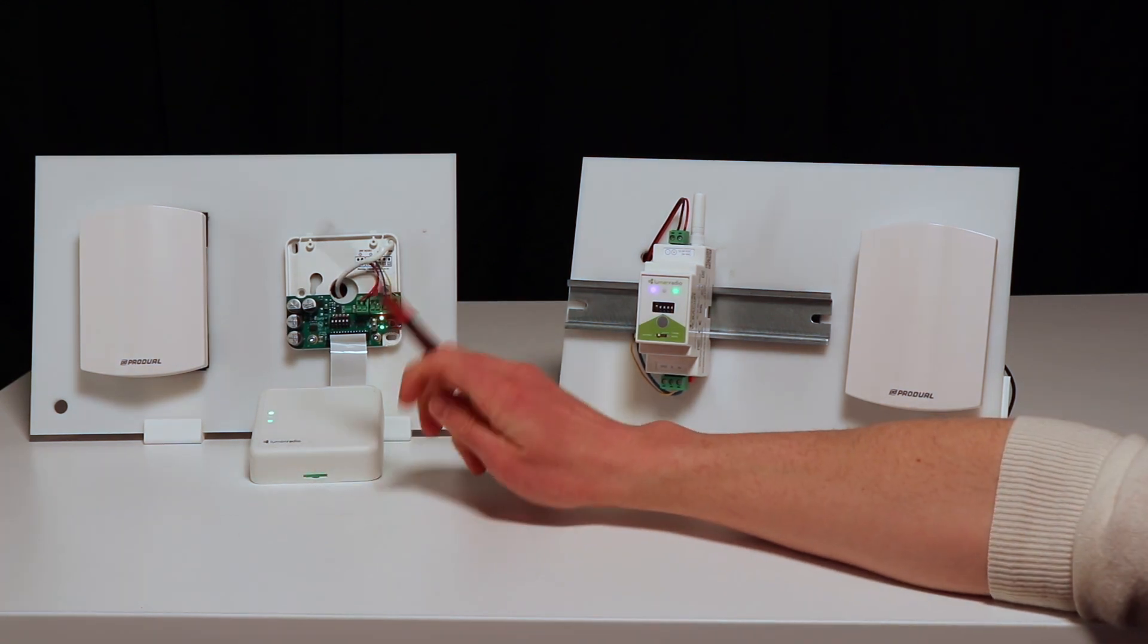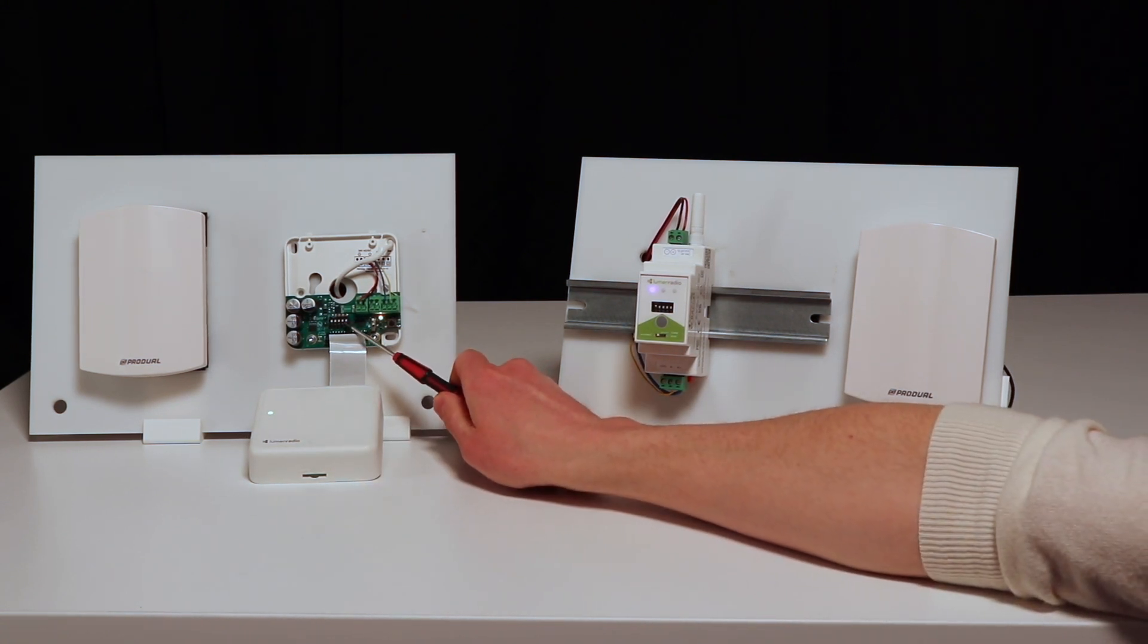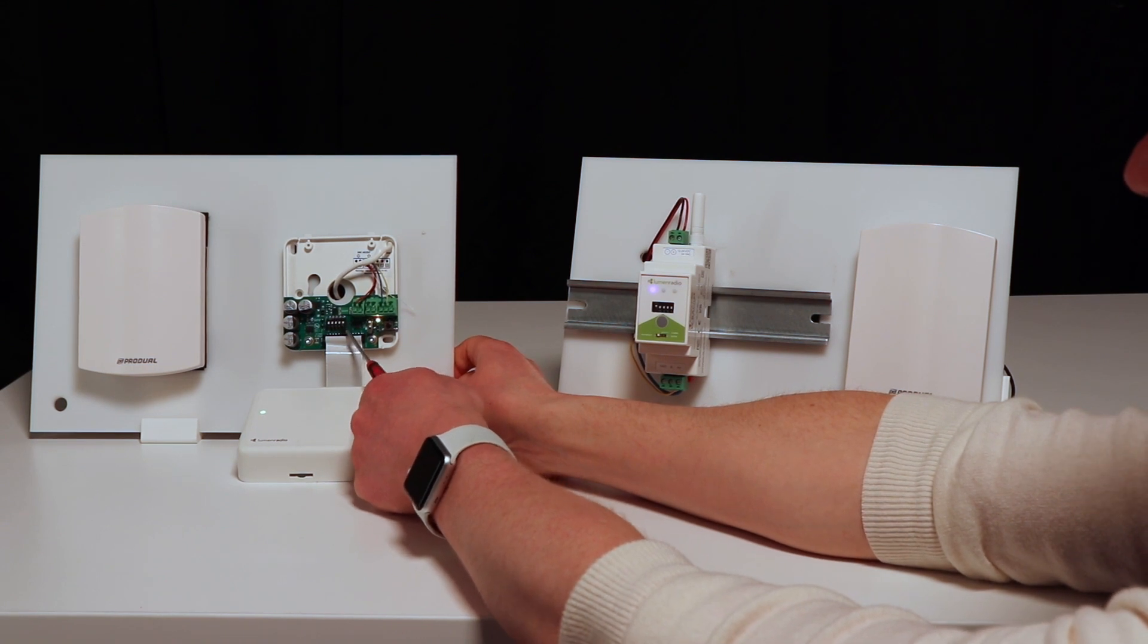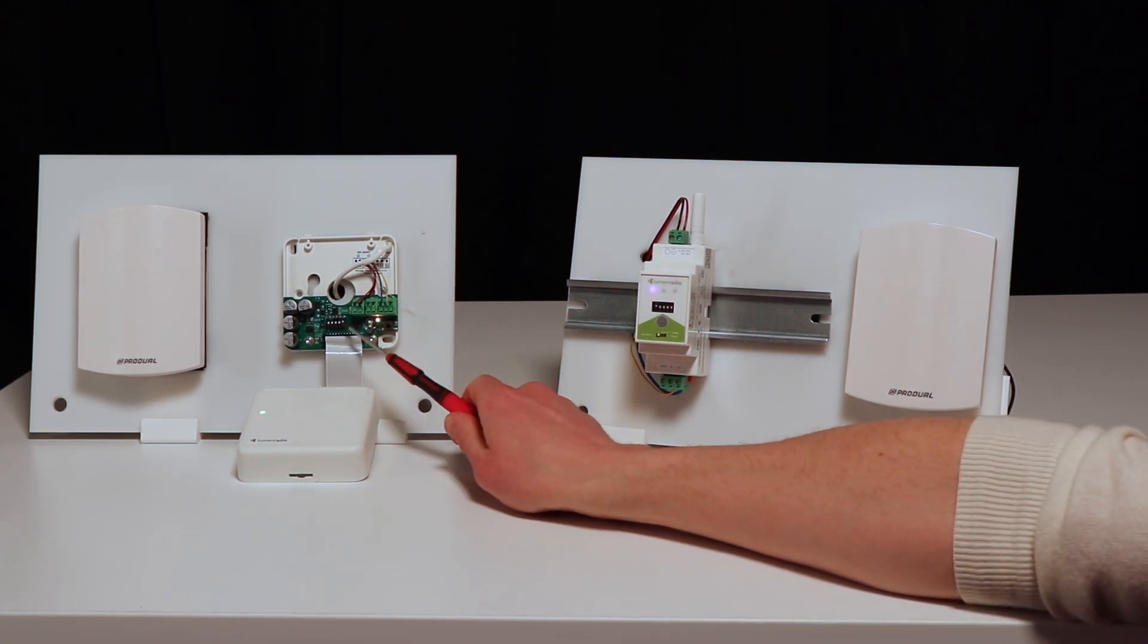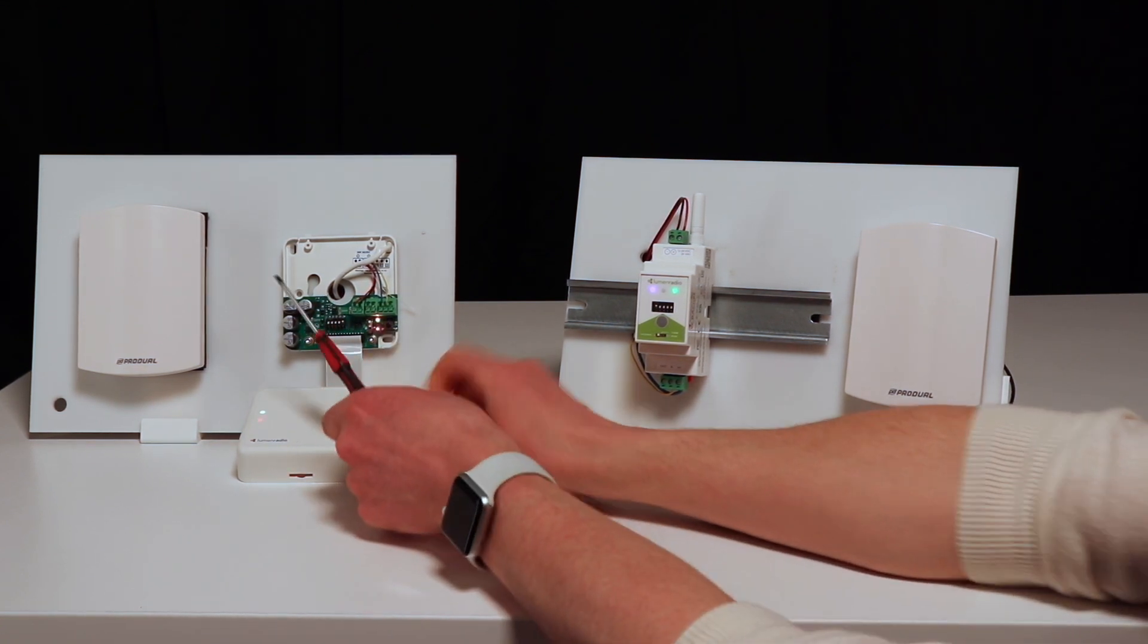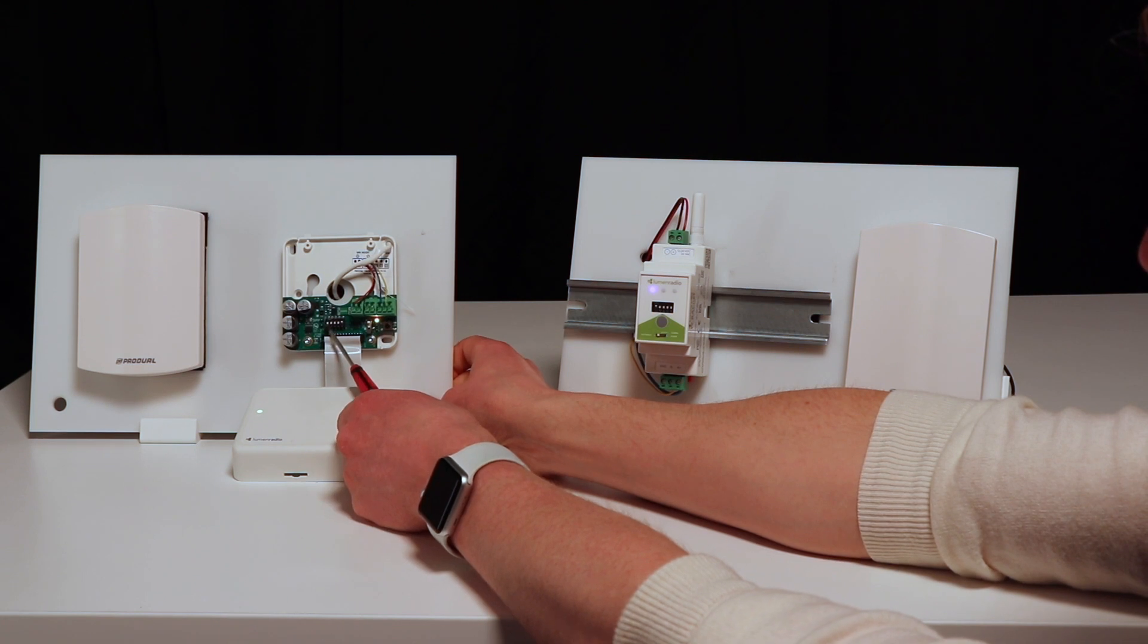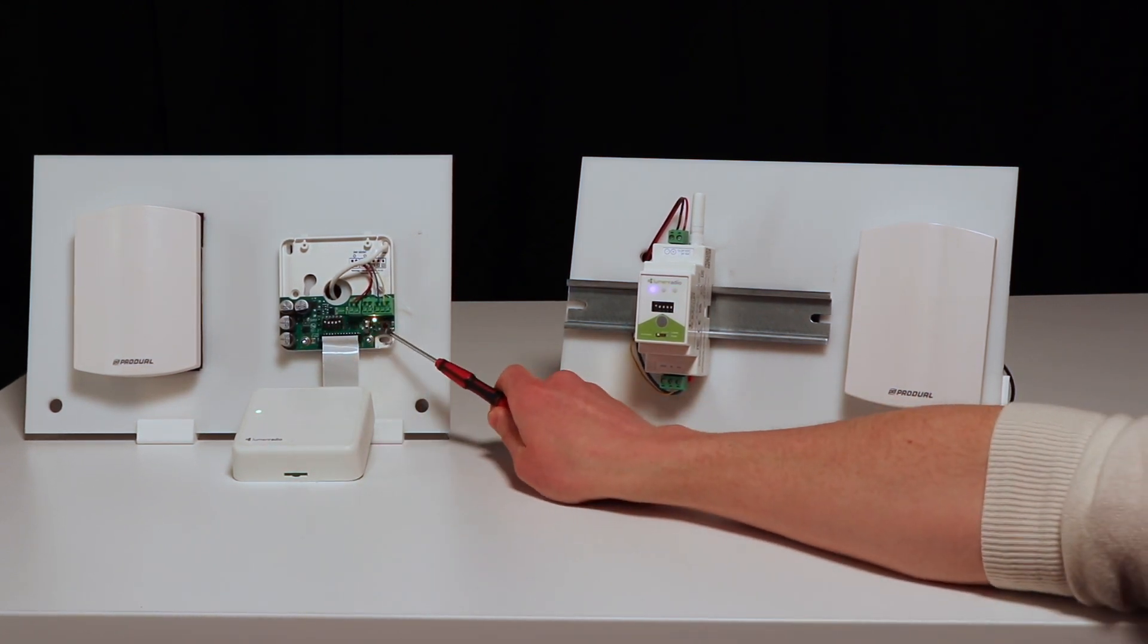If you want a specific node setting, you turn DIP switch 5 up. Now you will see that with 9600 it will again show red. So if you want to retain local settings, you could push this one up to 38400 and it turns green again.